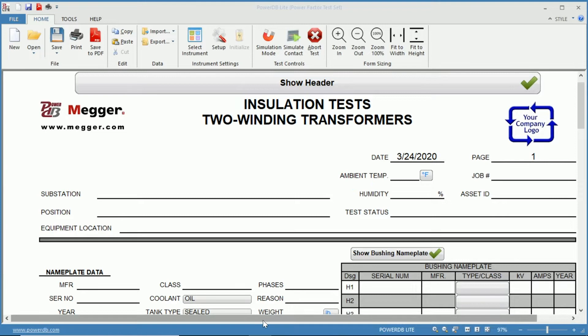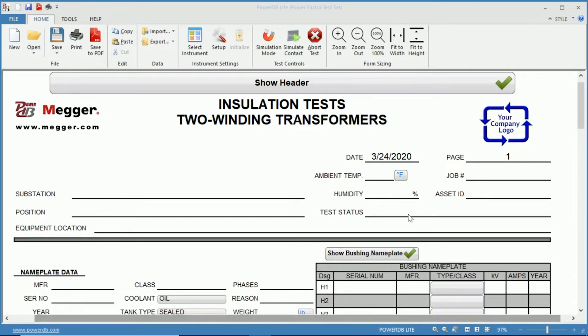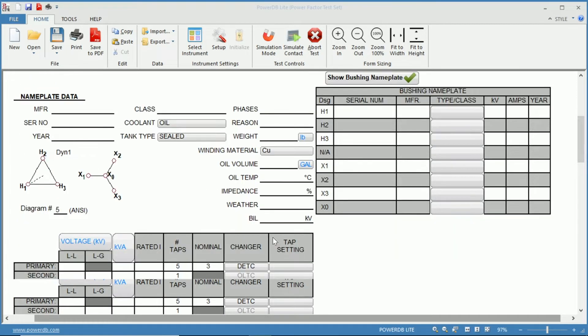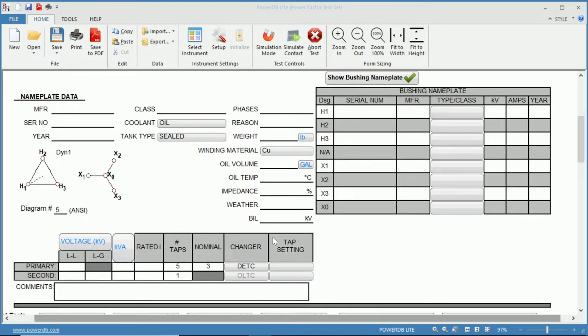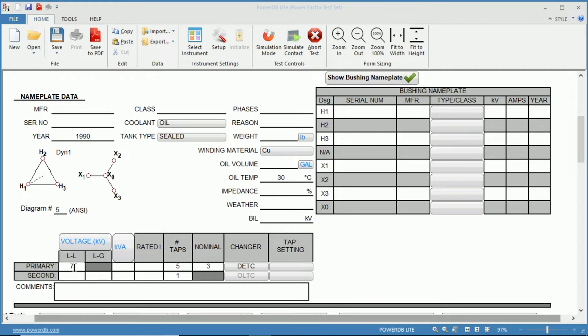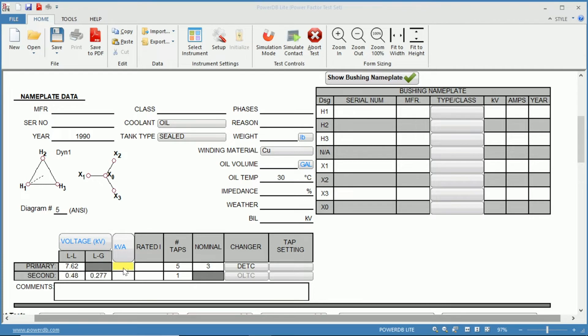With the test form open we can see the header information up top and the nameplate information. For temperature correction you need four pieces of information. This was covered in the using the temperature table charts as well. So let's say 1990 oil temp 30 degrees, then voltage is needed so let's do 7620 primary to a 480 volt secondary. We get the line to ground voltage and then we put in 30 kVA.